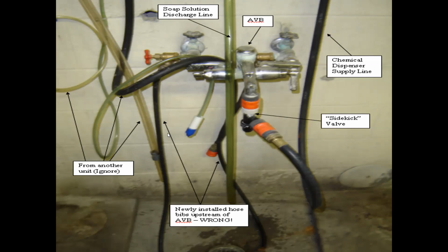And then you see there's still this kind of plastic attachment sticking down below it. That's what's basically going to allow this to discharge water without building pressure back up the hose line. And actually, this sink itself has an atmospheric vacuum breaker included on it. So we should have a certified chemical dispenser up above it, and we have an atmospheric vacuum breaker here.